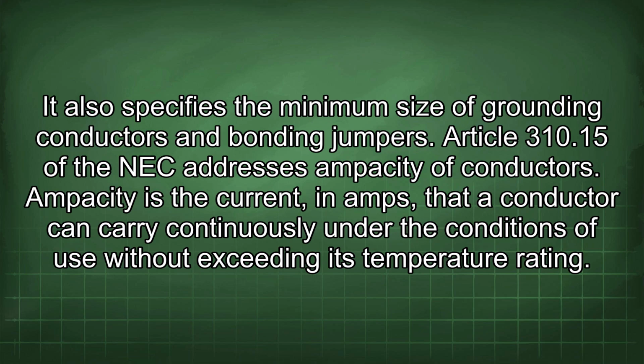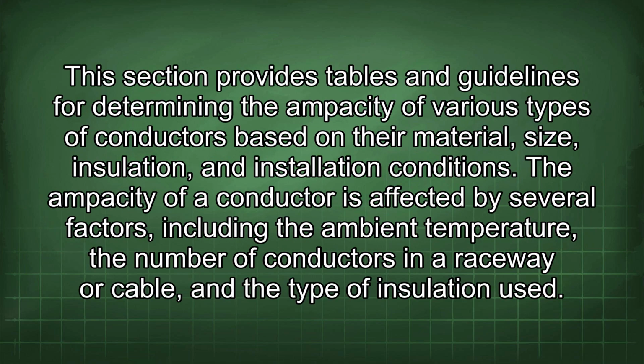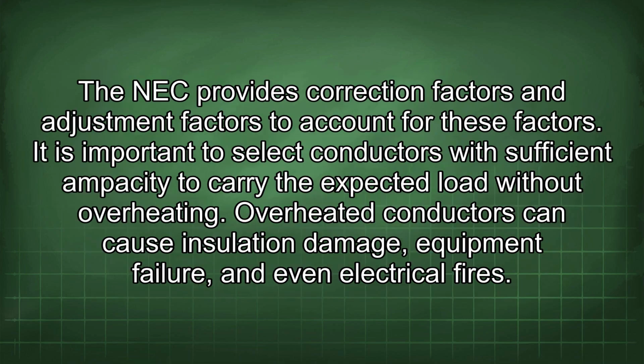Ampacity is the current, in amps, that a conductor can carry continuously under the conditions of use without exceeding its temperature rating. This section provides tables and guidelines for determining the ampacity of various types of conductors based on their material, size, insulation, and installation conditions. The ampacity of a conductor is affected by several factors, including the ambient temperature, the number of conductors in a raceway or cable, and the type of insulation used. The NEC provides correction factors and adjustment factors to account for these factors.